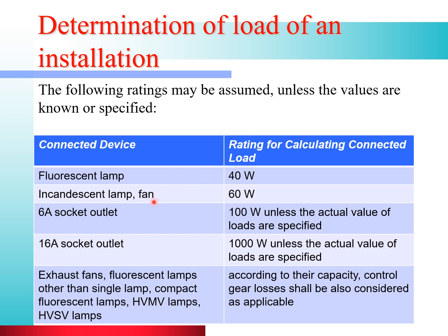The second device is the incandescent lamp and fan, with a rating of 60 W. For a 6-ampere socket outlet, the rating is taken as 100 W unless the actual value of the load is specified. For a 16-ampere socket outlet, 1000 W unless specified. Other devices listed include exhaust fan, fluorescent lamps other than single lamp, compact fluorescent lamp, HVMV lamp (high voltage mercury vapor) and HVSV lamp (high voltage sodium vapor). According to their capacity, control gear losses shall also be considered as applicable.